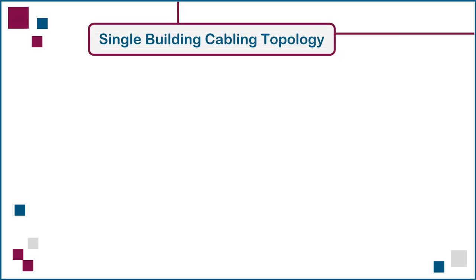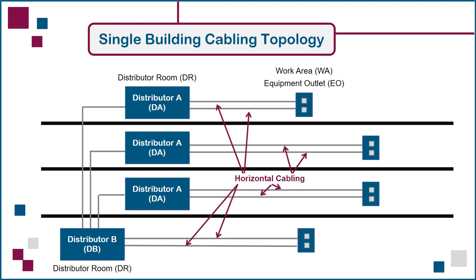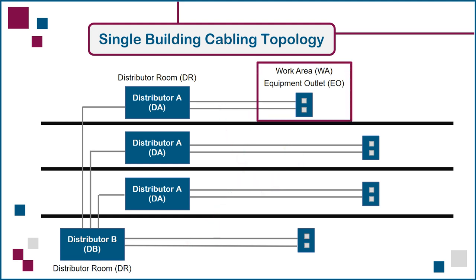Let's now look at the generic cabling model as applied to a single-building environment. In this side view of a four-floor building, backbone cabling links Distributor B in the building's distributor room to individual Distributor A's in distributor rooms on each floor. The second link in the chain is horizontal cabling, linking Distributor A on each floor to each of the equipment outlets on the same floor. Note that historically, equipment outlets were associated with individual work areas, such as enclosed offices and open cubicles. In today's intelligent buildings, outlets are likely to be located everywhere, to enable connections of network devices such as security cameras, building controls, lighting, and audio-video equipment such as digital signage screens.